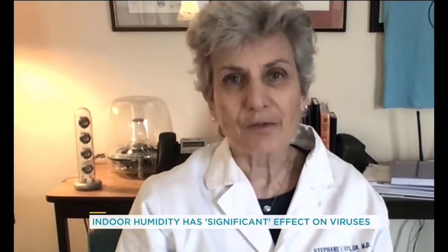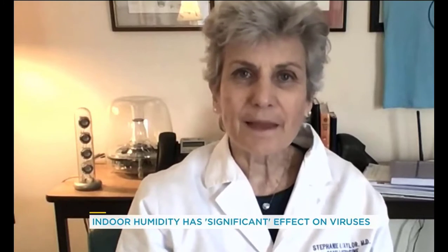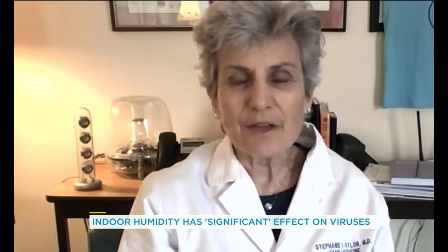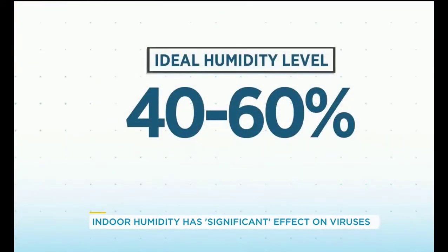This is a fascinating angle to this story. You say humidity has a three-pronged relationship with viruses. What can you tell us about that? Yes, it is absolutely exciting and effective. We now know after many years and numerous studies that viruses are actually diminished in the airborne environment when you have the proper range of humidity, and that happens to be a very comfortable mid-range of 40 to 60 percent relative humidity. In this range, we now know that the air actually has fewer infectious particles.